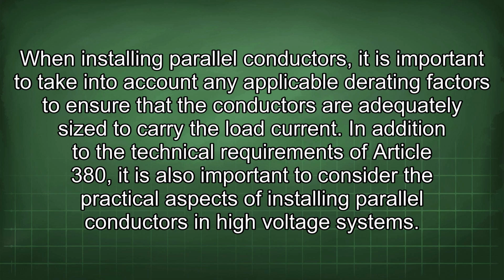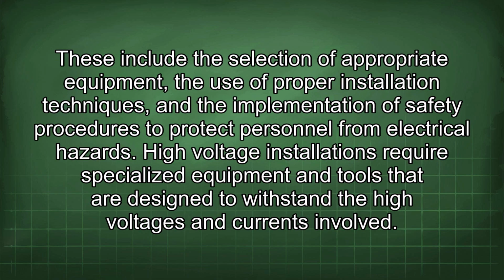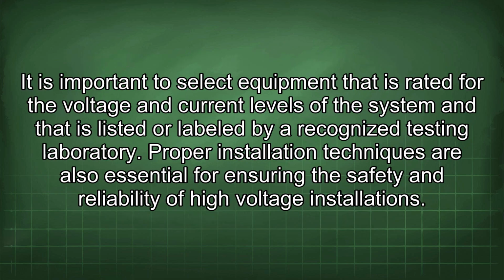In addition to the technical requirements of Article 380, it is also important to consider the practical aspects of installing parallel conductors in high voltage systems. These include the selection of appropriate equipment, the use of proper installation techniques, and the implementation of safety procedures to protect personnel from electrical hazards. High voltage installations require specialized equipment and tools that are designed to withstand the high voltages and currents involved. It is important to select equipment that is rated for the voltage and current levels of the system and that is listed or labeled by a recognized testing laboratory.